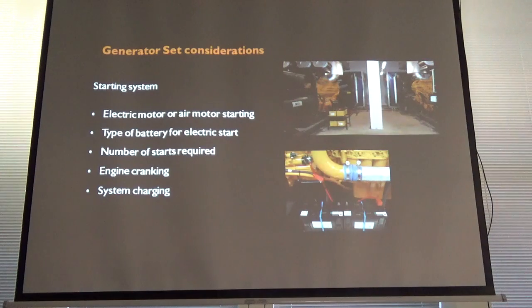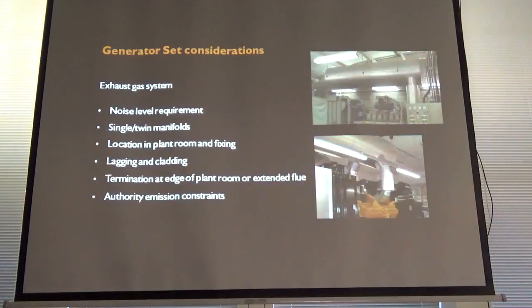And normally with larger units you might get 2 starters or even 3 starters. They'll gang them together because again it's to do with life and resilience. You might have a set with 3 starters, but if one fails it'll fail safe. The 2 starters will still have enough capacity in them to still turn over the unit. That's often tested at hospitals as well. So again, belt and braces, resilience, failing safe, all these sorts of aspects that are considered.